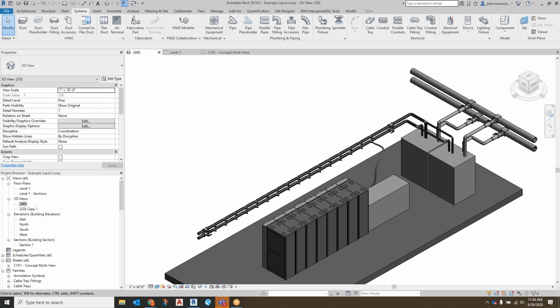Now, you've also done designs that don't use CDUs. Would you always use a CDU just to isolate the volume at the very least? No, we've used chilled water, elevated chilled water, and also condenser water directly to the cabinet, to a rear door heat exchanger. Right, so a couple different things we're talking about here.